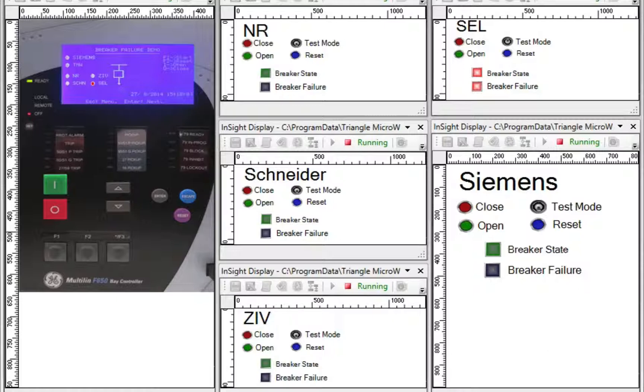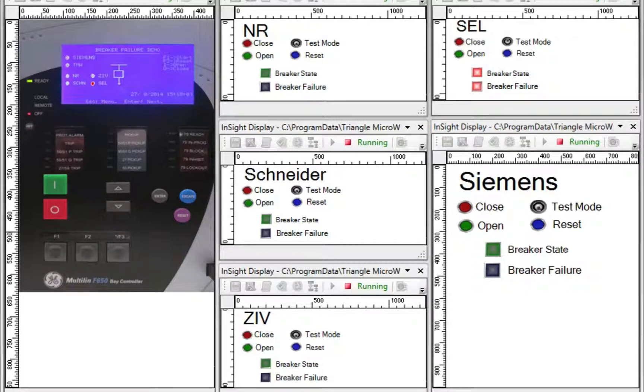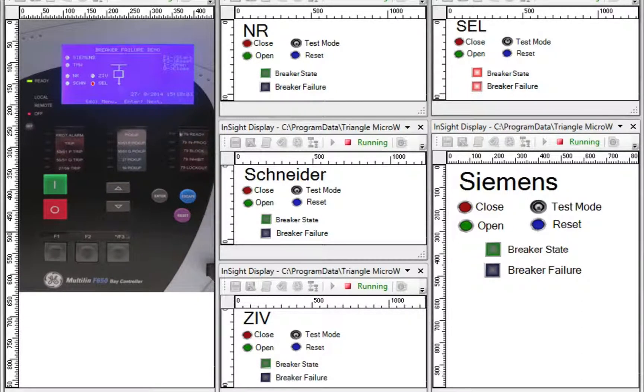These front panel updates are driven by Insight, the graphing component available with DTM, the 61850 test suite, IRN, our ICCP TASE.2 test tool, the communication protocol test harness, and the SCADA data gateway. The breaker status and breaker failure indications reflect the values of the data attributes they are mapped to in the IEC-61850 object model. A server display will typically reflect the data attributes that are sent by IEC-61850, and a client display will reflect data attributes that were received by IEC-61850.